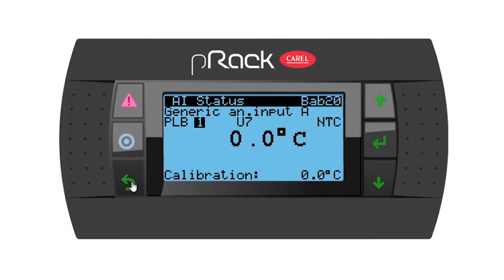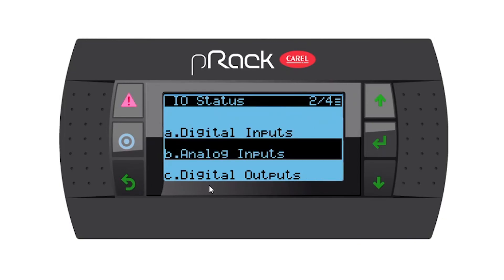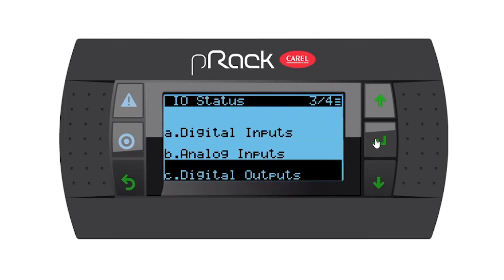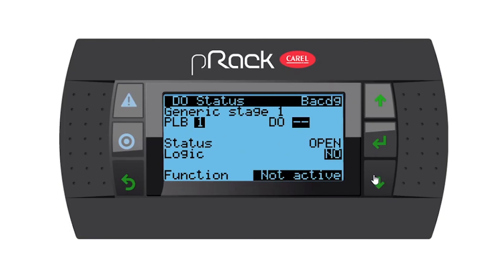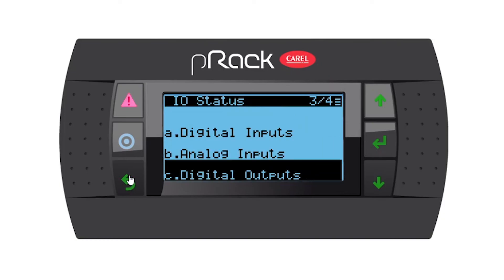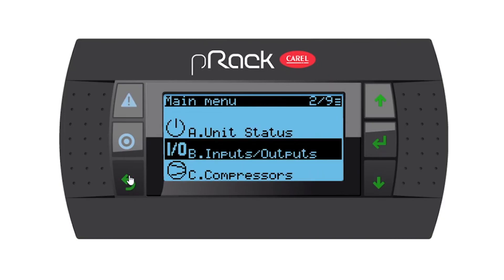Now the controller knows what input to look at. We need to assign the output — go back one and go down to digital outputs. We're going to assign the output that will actually click our solenoid. Going down, there are compressors, fans, and generic stage number one — I'll enter and assign it to digital output number six, normally open, and the function is not active.